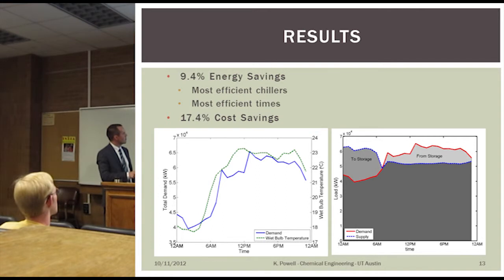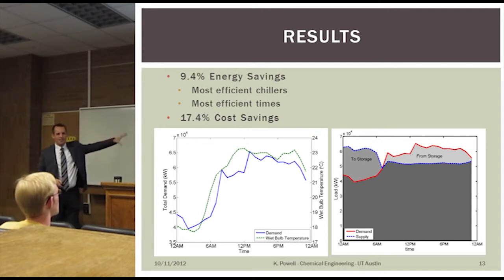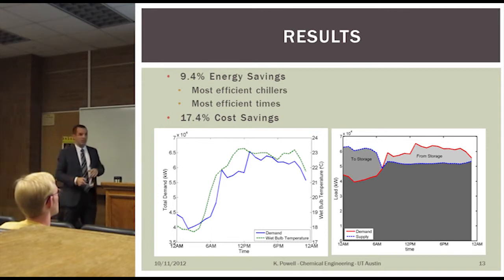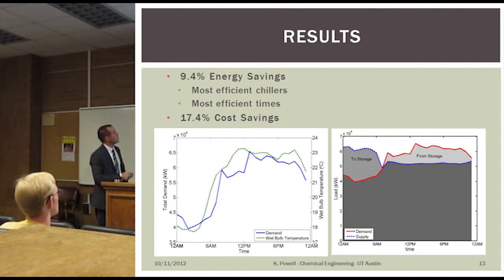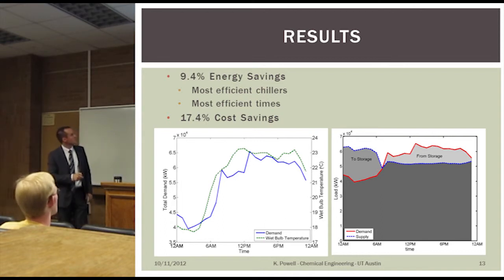Our wet bulb temperature increases like this, and this is what our demand is going to do for the next 24 hours. If we take that, we can run our dynamic optimization to figure out how to use the storage optimally. We get a 9.4% energy savings because now we're not just shifting to our most efficient chillers, we're also shifting a lot of our demand to the most efficient times, minimizing energy of our chiller system.